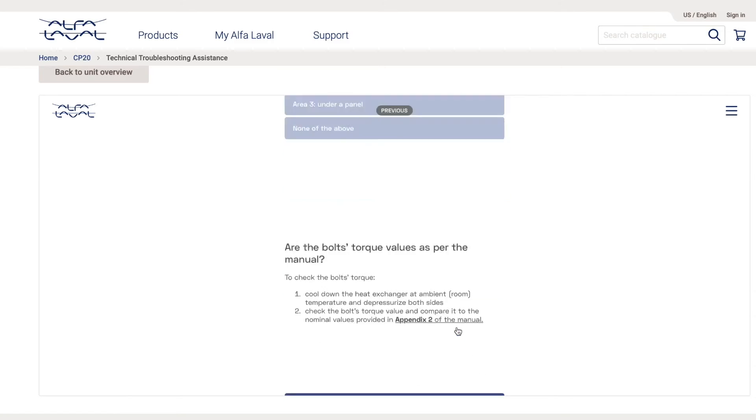So I read number three, and then I have a first question. Are the bolts torque values as per the manual? I can check the values by opening the instruction manual and read appendix number two. Let's say the values are identical.